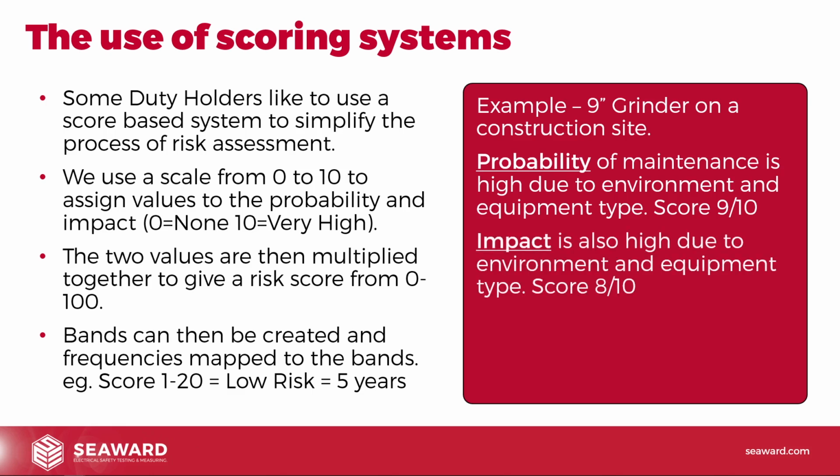Now, impact. What could be the problems if there is maintenance required with this grinder if it does go wrong? So again, due to the environment that we're actually in, we're in a building site. You could be in a wet, muddy puddle. If somebody's going to get electric shock out of that, and also the equipment type, it's handheld equipment. So if we've got handheld equipment, it's going to be in my hands. I'm standing on a wet, muddy building site, maybe in the rain, using this thing. Something goes wrong with it, I could get injured. In fact, there's a very high probability that I would be injured.